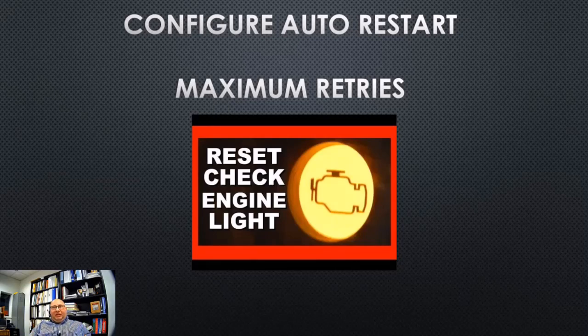There's a 3 to 10 second delay. If there's truly a problem, it's going to try to restart 10 times and then physically lock out permanently, and then it'll give you a failure alarm. But let it try to restart. There might be a temporary brownout. It might be a temporary voltage imbalance. It could be a temporary line problem. We don't want to go back for nuisance service calls if it's not necessary. And we also want to maybe allow it to do a direct run after power up.